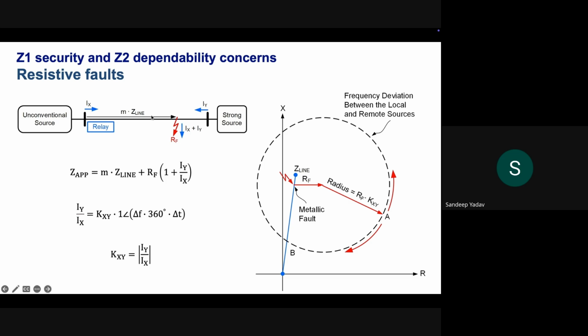If the fault is at 60%, then definitely from this point up until the fault point, the impedance will be 0.6 of the total, or 60% of the total line length. So the total apparent impedance is M into Z line plus RF, the fault resistance, into 1 plus IY upon IX. IY is the contribution from the remote end, and IX is the current seen at the relay terminal. So the apparent impedance is M into Z line plus RF, the fault resistance, and the current going into the fault is IX plus IY. So now, if you take a look at this mathematical expression, IY upon IX.